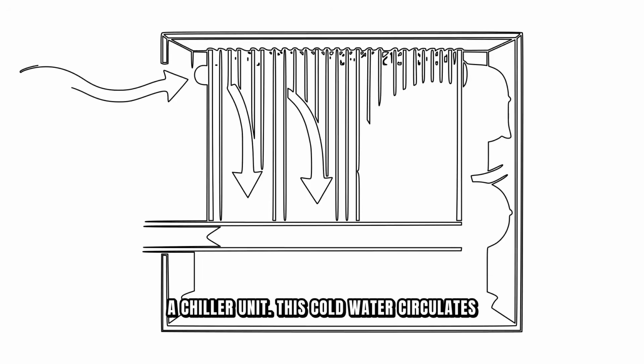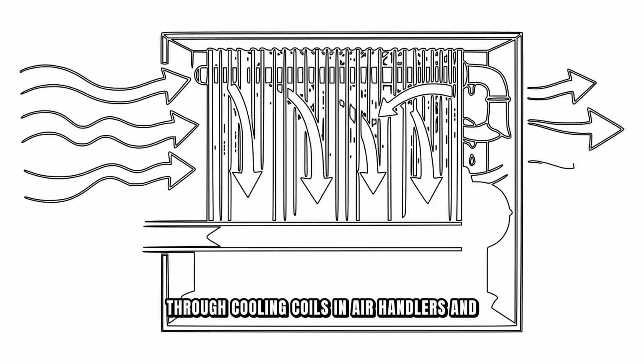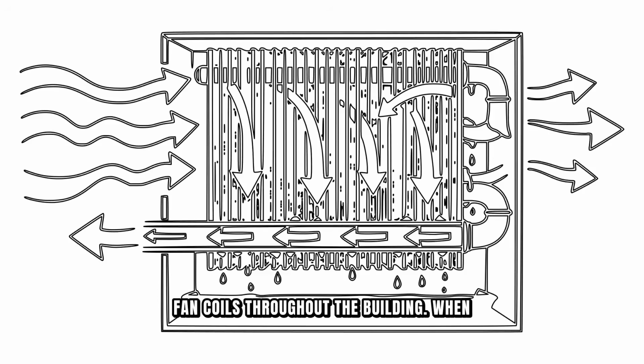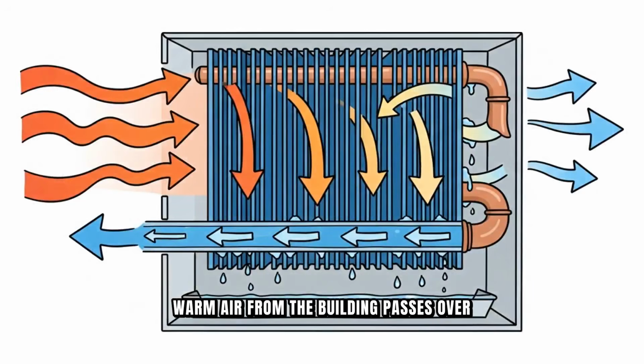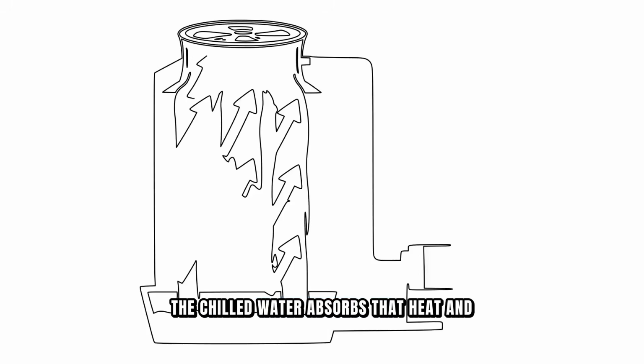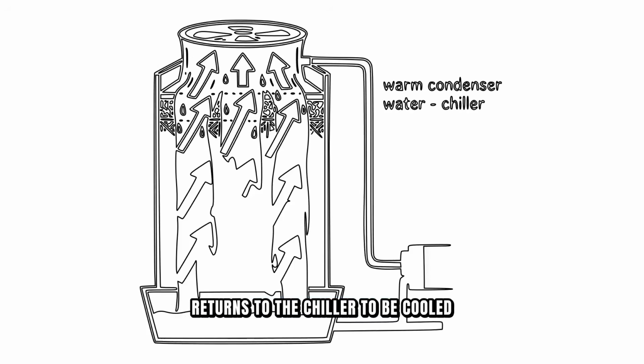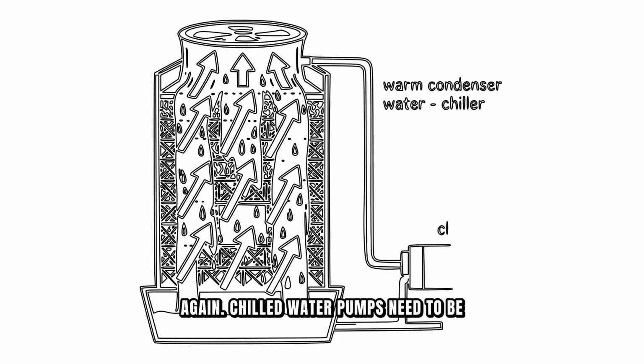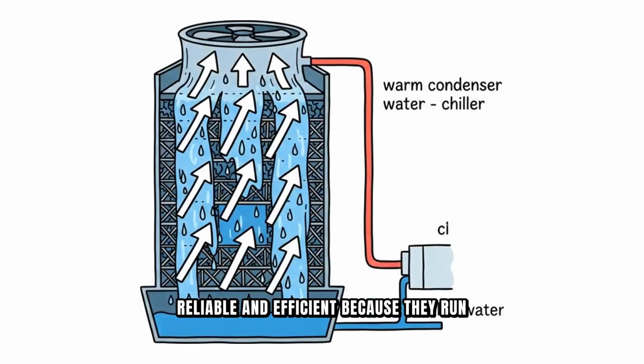This cold water circulates through cooling coils in air handlers and fan coils throughout the building. When warm air from the building passes over these cold coils, heat transfers from the air to the water. The chilled water absorbs that heat and returns to the chiller to be cooled again. Chilled water pumps need to be reliable and efficient because they run almost constantly during summer months.